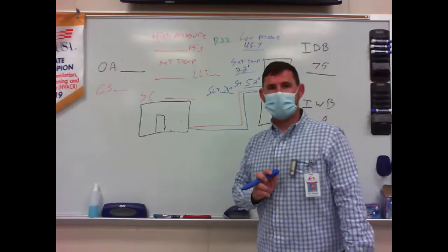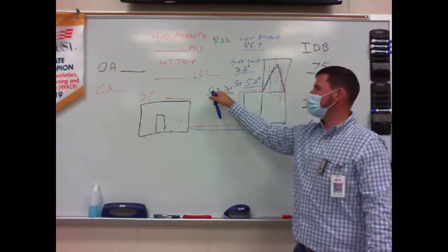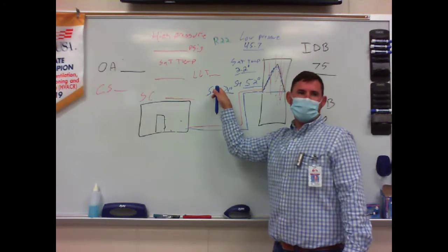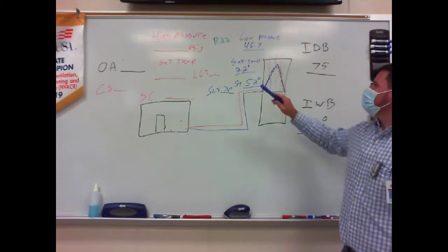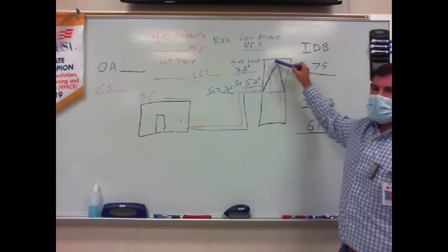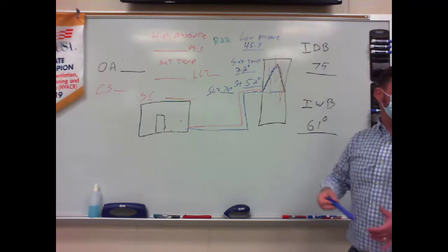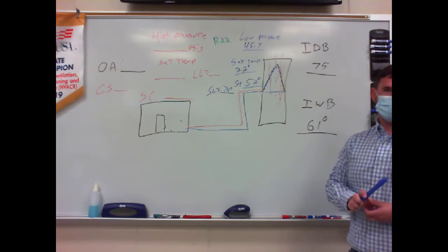That's what? More than I've ever seen. More than you've ever seen? Well, this line temperature is 74 degrees because that's what the room temperature is. So there's not even enough refrigerant in there to really cool that line off much. So is this starved of refrigerant inside this evaporator coil, or is it an airflow or dirty coil issue? I'm starved of refrigerant, right?